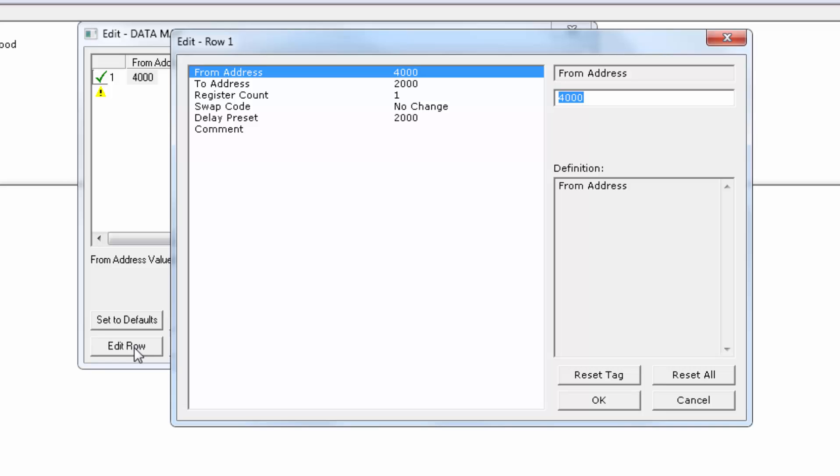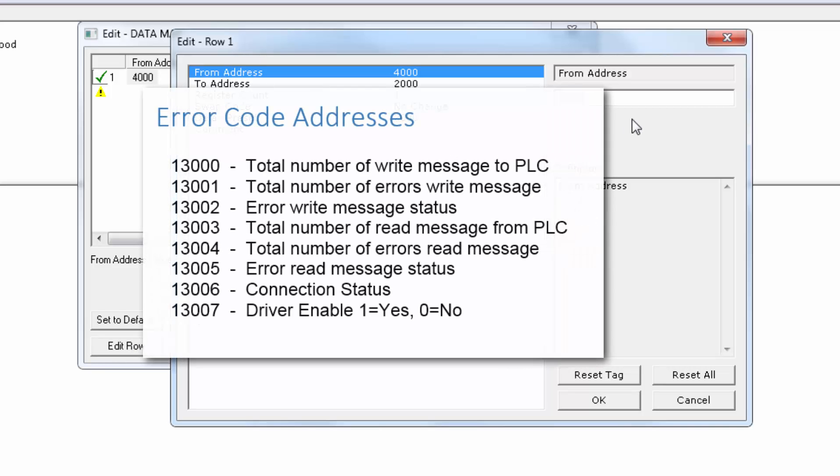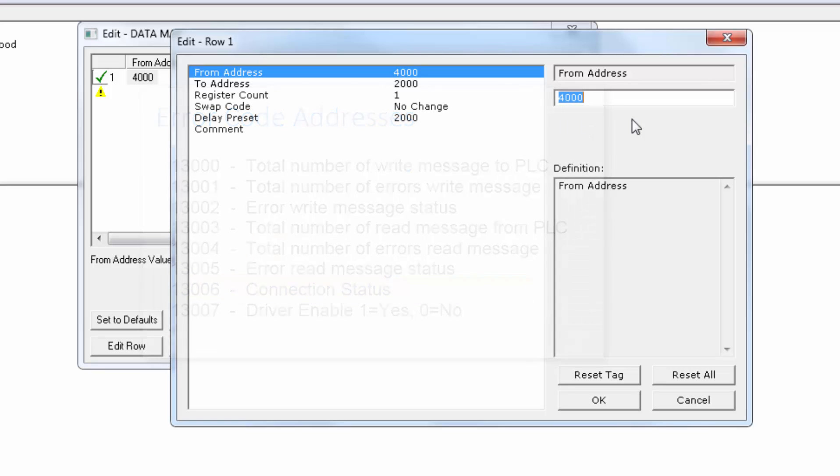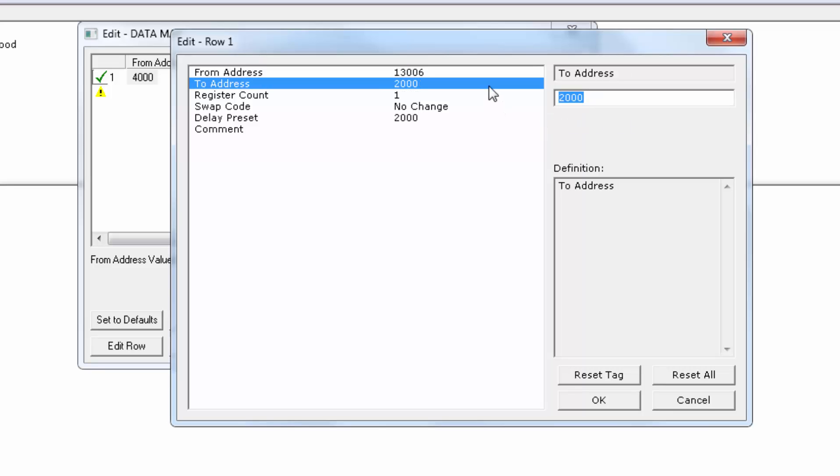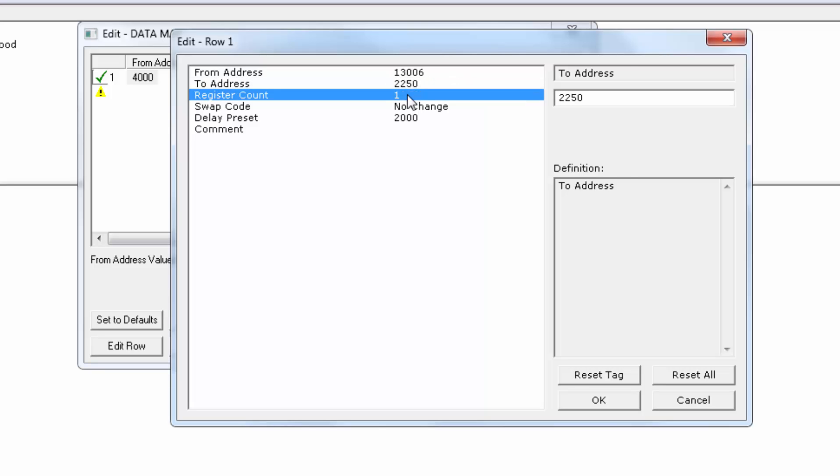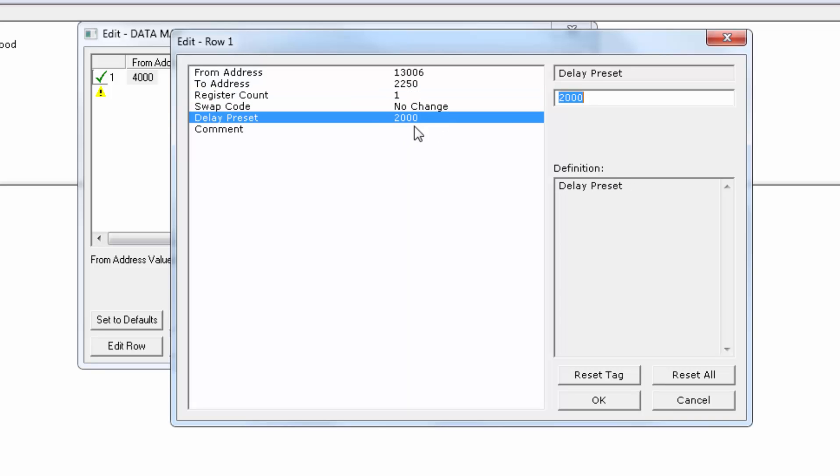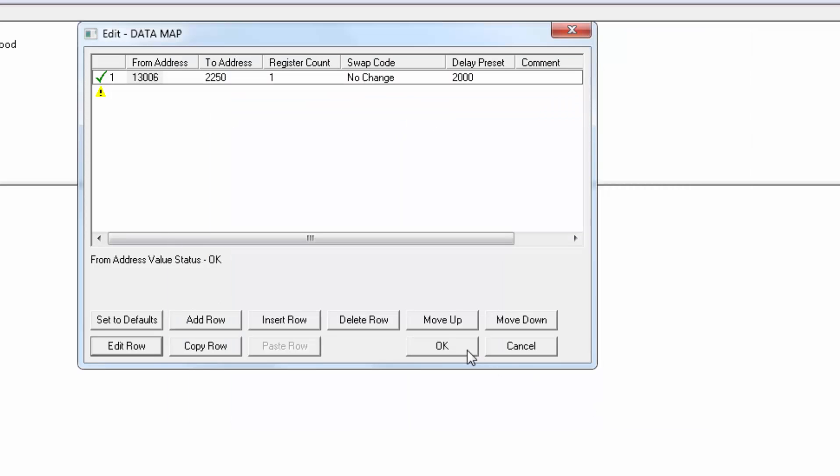The only status I'm concerned with on the PROFINET side is the state of the connection. So we'll map in from address 13,006 to address 2,250 with a length of 1. This will let us know if our module loses communication with the PROFINET controller.